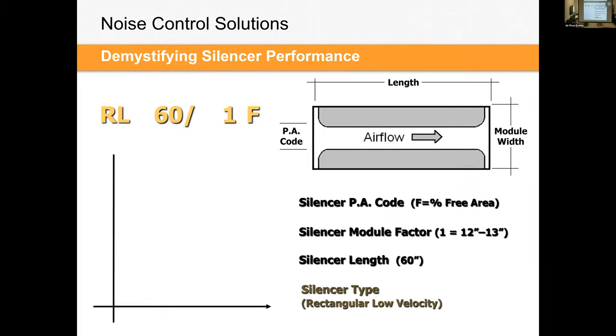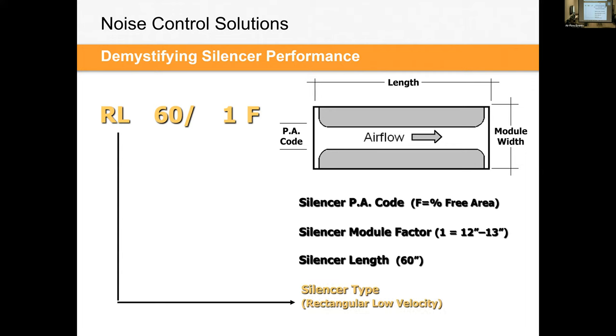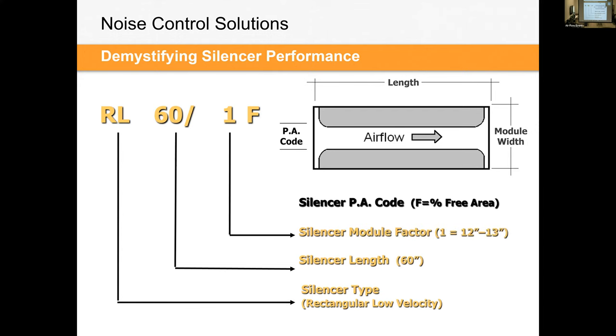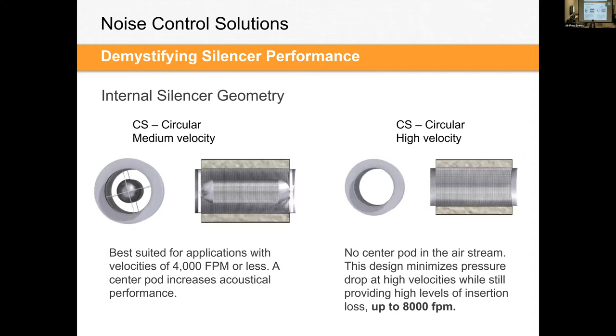All of these things I just went through break down into that silencer model code. So the RL is that low velocity parallel baffle type. The length is that 60, that would be 60 inches long. The one would be that module factor. In this case, that would be a 12 inch wide. And then the PA code in this case would be an F or 25% free area. So when you see this RL 60/1F, that's what it is: these different factors and modules and lengths and acoustic media types. So a bit convoluted, but hopefully that gives you a really good understanding.